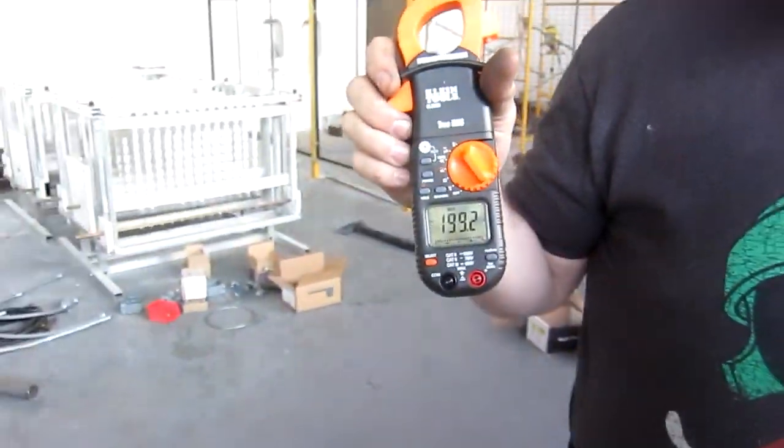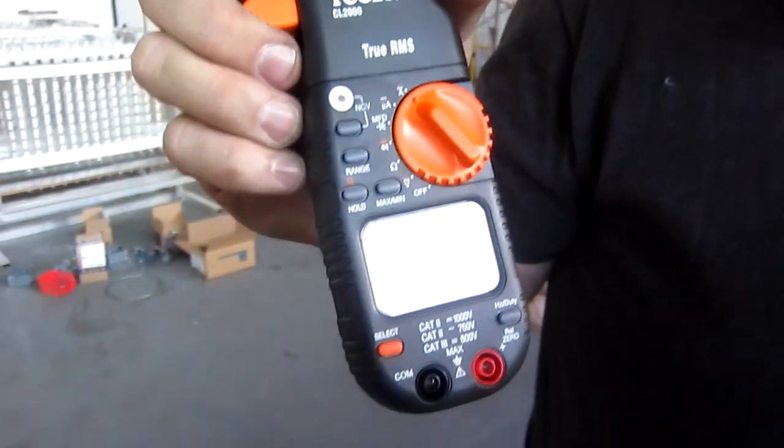It is 1835 hours. We've got a CL2000 meter holding max amperage — you can see it's set to current and reading 199.2 amps, and we still have plenty of variac left to go. We think we're only at about 50 percent. We need more inductive reactance — 480 volt inductive reactance. What we've got in there now isn't much of a reactor. If you put inductors in series you get more reactance — let's series them, should take about five minutes.